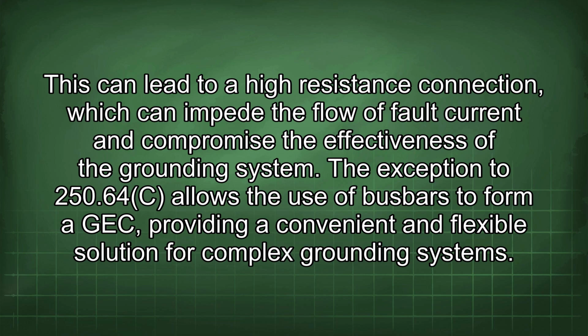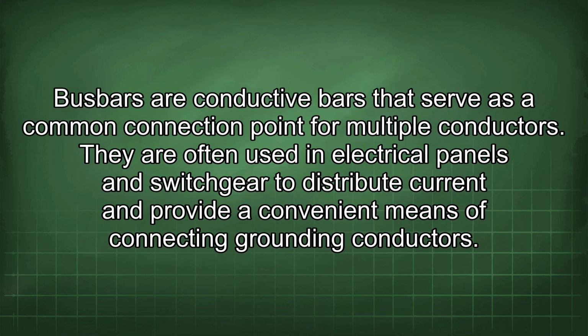The exception to 250.64(C) allows the use of busbars to form a GEC, providing a convenient and flexible solution for complex grounding systems. Busbars are conductive bars that serve as a common connection point for multiple conductors.